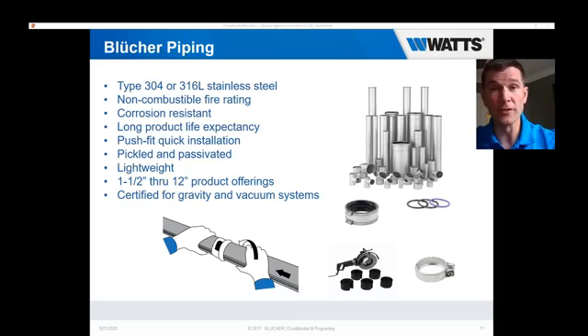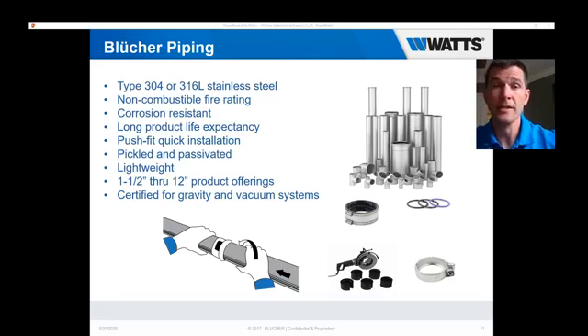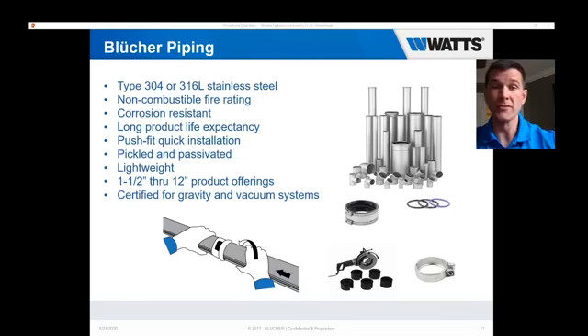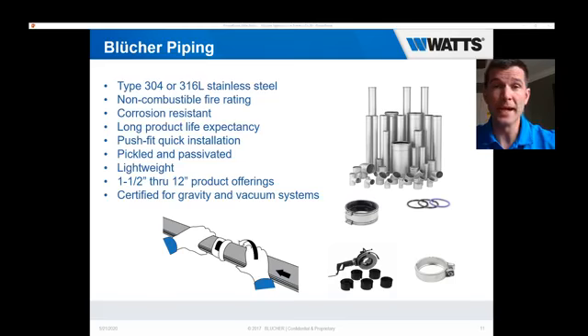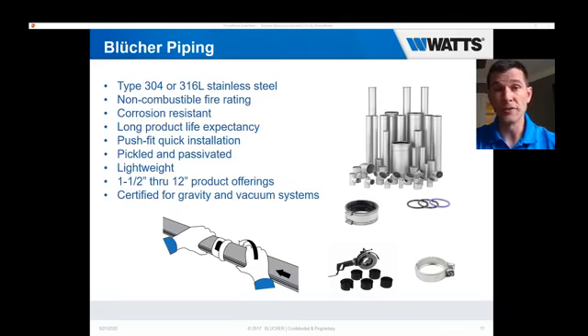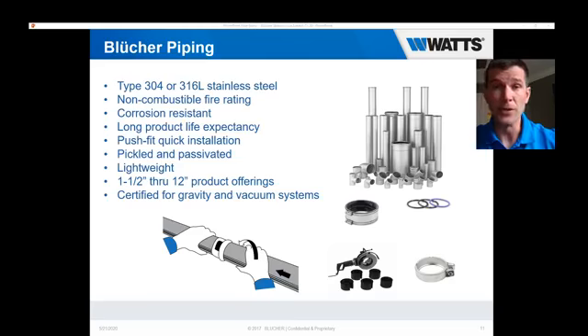Another key aspect for Blücher — not only siphonic roof drainage but all roof drainage — is our push-fit piping. It comes in 304 or 316 stainless steel. For buildings, it is non-combustible, fire rated, very corrosion resistant, and has a long life. The push-fit installation is a very fast connection — there's no welding, no clamping or coupling required. It is pickled and passivated, meaning it has a chromium oxide coating covering the pipe, giving it more resistance, more strength, and more longevity. It is offered in one-and-a-half to twelve inch; in a siphonic system, generally two, three, four, or six inch piping would be used.